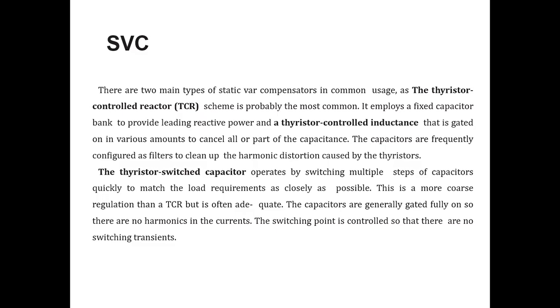Next is the SVC, that is, static var compensators. Static var compensators are of two types: thyristor controlled reactors, that is, thyristor controlled inductors, and TSC, that is, thyristor switched capacitors. So there are two main types of static var compensators in common usage. The first is the thyristor controlled reactor, and the second is the thyristor switched capacitor. The thyristor controlled reactor employs a fixed capacitor bank to provide leading reactive power, and a thyristor controlled inductance that is gated on by various amounts to cancel out parts of the capacitance. The capacitors are frequently configured as filters to clean up the harmonic distortion caused by the thyristors.